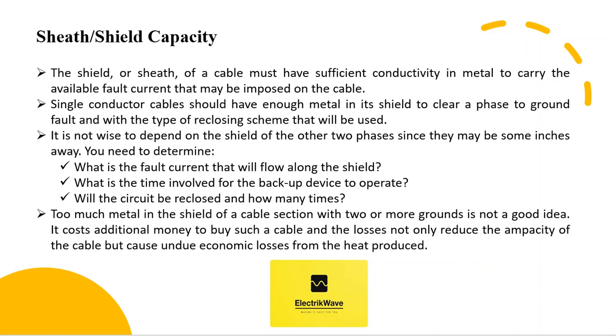You need to determine: what is the fault current that will flow along the shield, what is the time involved for the backup device to operate, and will the circuit be re-closed and how many times? Too much metal in the shield of a cable section with two or more grounds is not a good idea — it costs additional money, and the losses not only reduce the ampacity of the cable but cause undue economic losses from the heat produced.